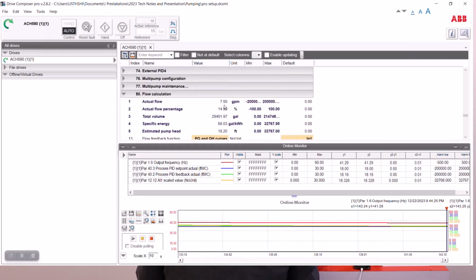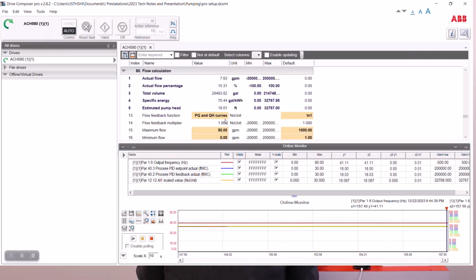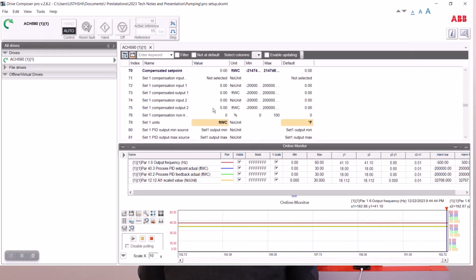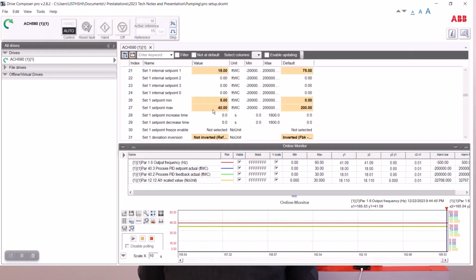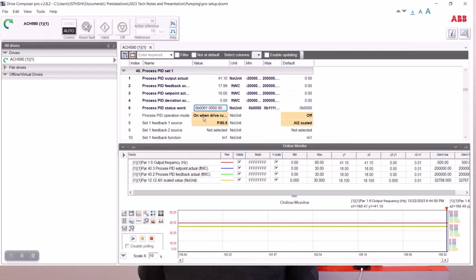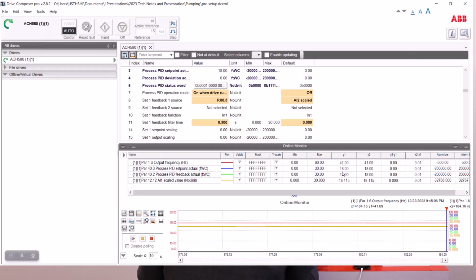And it's claiming theoretically that it's got 7.65 gallons a minute, and by calculation it's a bit off right now. They're only doing about 6-point-something gallons per minute right now. But that's a calculation base there. It's not actual flow. It's what it's calculated at. But it's still starting to stabilize out. I get back down to my PID loop area right here, and when we look at it, it's looking at 41 hertz, and that's 41 hertz there. I'm at 17, 18, and 18. So right off the bat, the system is stabilized at 18 feet of water column. So 18 feet of water column is what we stabilized at.